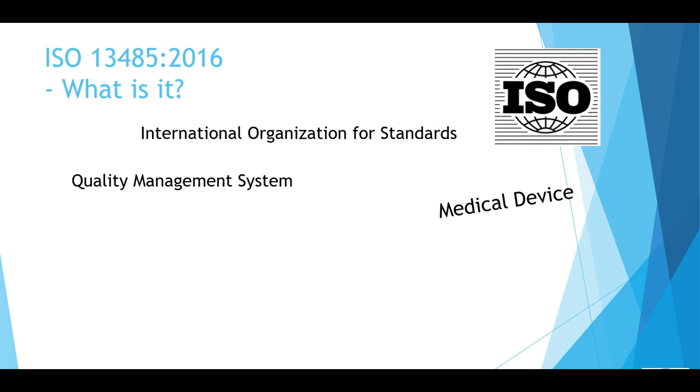By certifying an organization as conforming to the ISO 13485 standard, an accredited third-party body of auditors attests to the organization conforming to the quality management requirements of the standard, including being compliant with applicable regulatory requirements, which must be identified within the Quality Management System, or QMS.